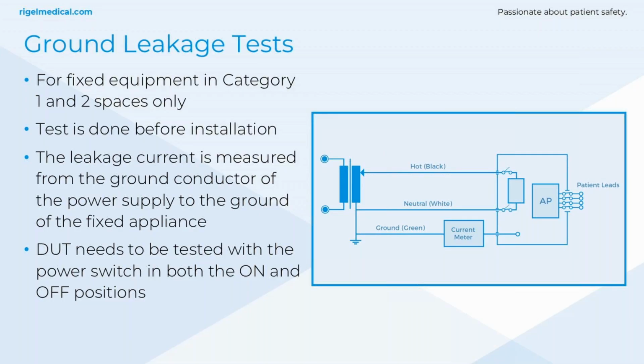One of the key things to ensure when doing this test with fixed equipment is that it's done before any grounds are connected. All the test is doing is measuring the leakage current from the ground conductor of the power supply to the ground of the device under test. Now, the current limit of this is quite high. It's 10 milliamps or 10,000 microamps. And you do this with the power switch in both the on and off positions.